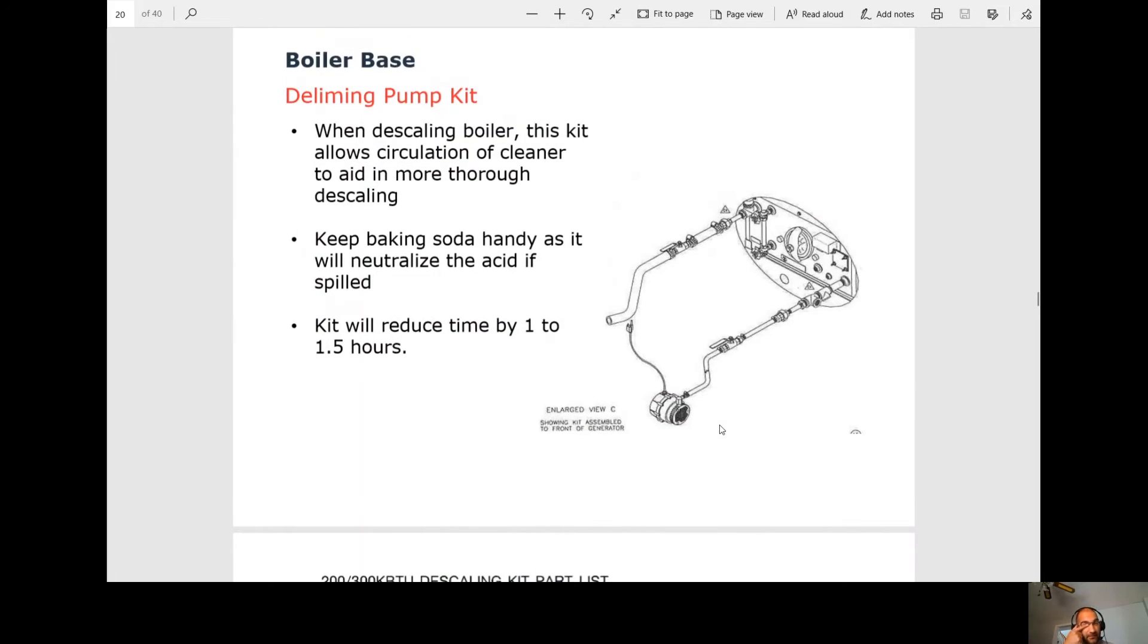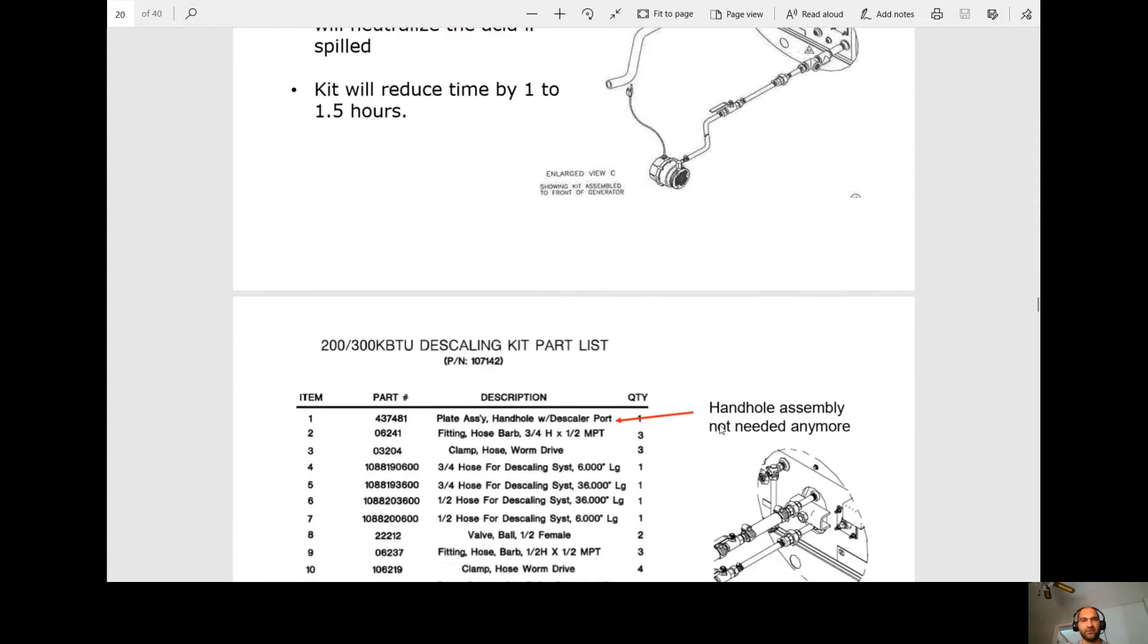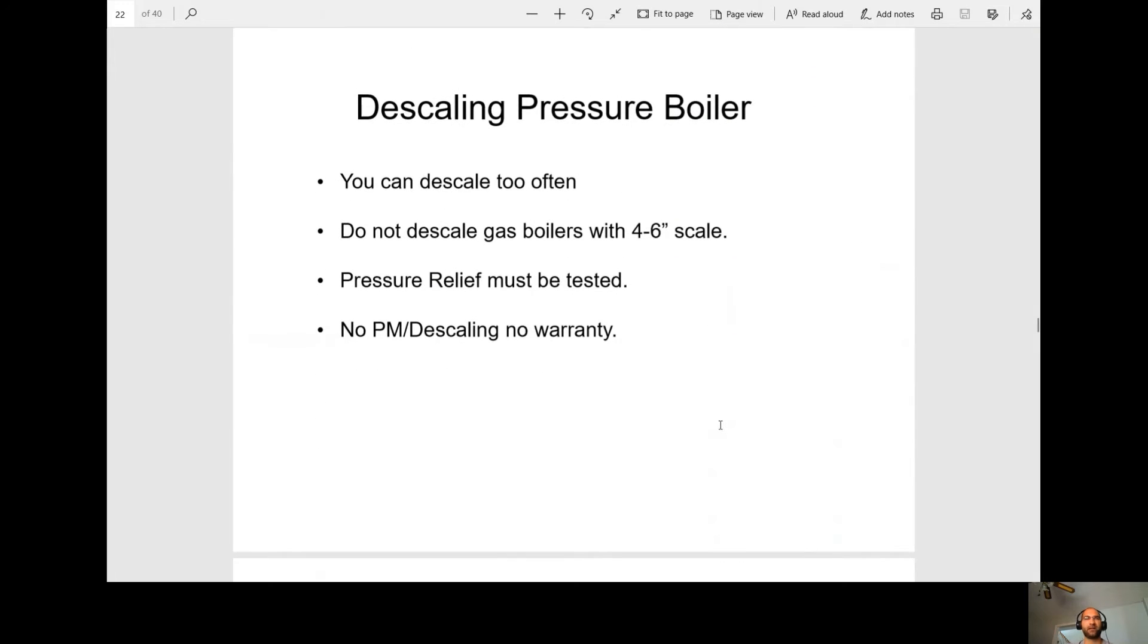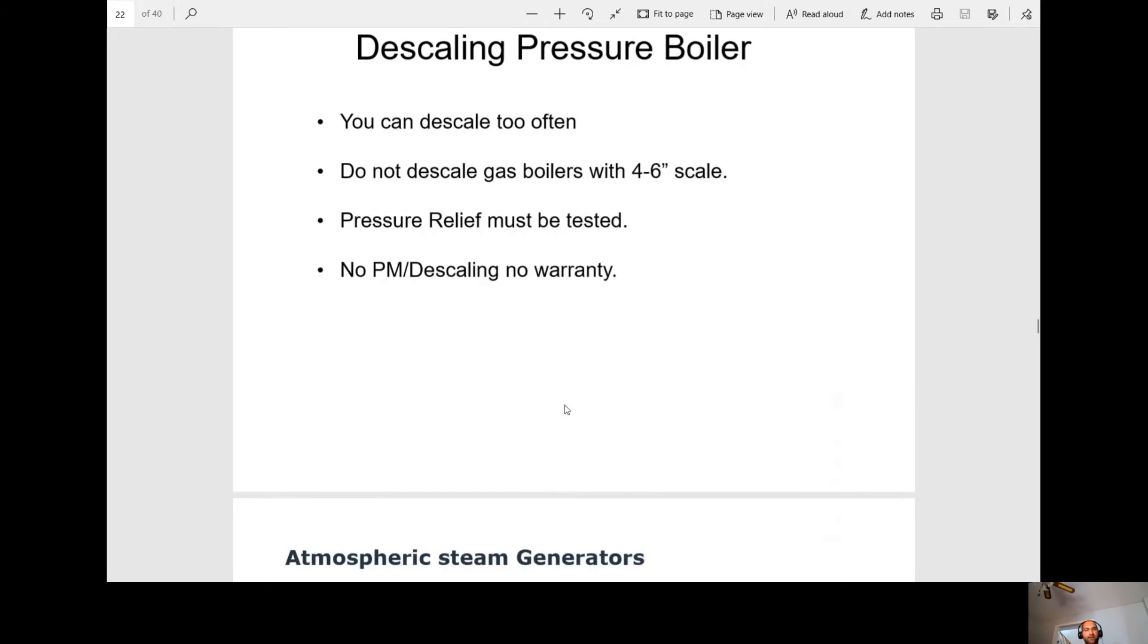Here they discuss a deliming pump kit just to make things a little bit faster. It's not something that we utilize. So just quickly, can you descale too often? Yes. The acids will attack the boiler walls. Any scale on a gas boiler, 4 to 6 inches thick, do not remove the scale. It'll most likely start leaking because it's probably acting as an insulator in whatever cracks might be in there. Pressure relief valve must be tested after every descale. And if they haven't been doing any PMs or descaling, the warranty would be voided at that point.